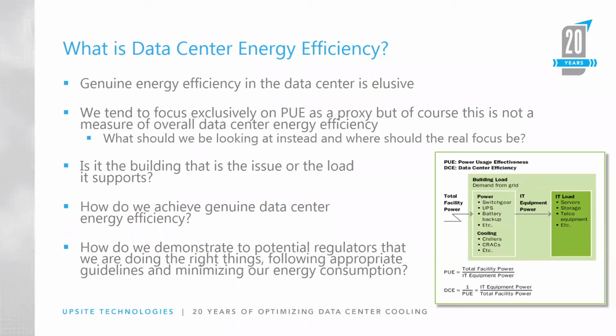We tend to focus on PUE as a proxy, and obviously I can't possibly do a data center presentation without talking about PUE, much as I hate having to do so, but we have to put it out there. We do use PUE as a proxy, but as I repeatedly say, PUE is not, and never has been, and never will be, a measure of data center energy efficiency.